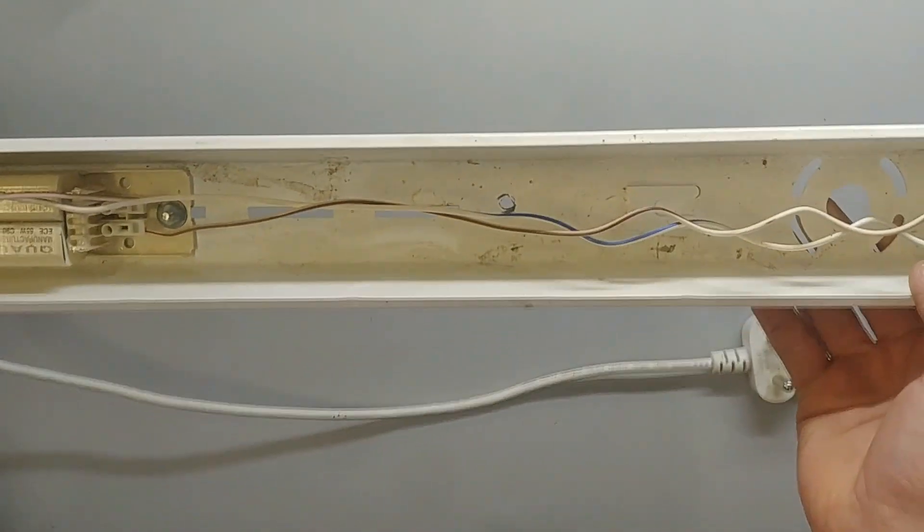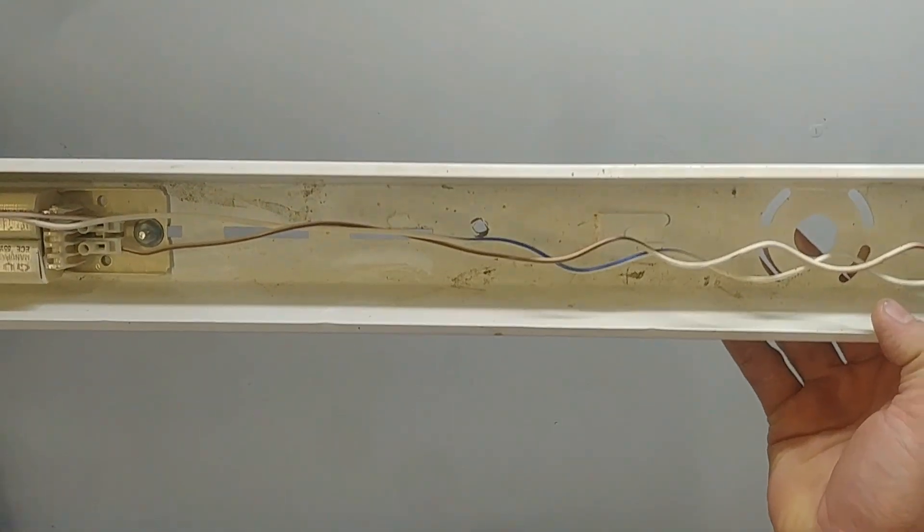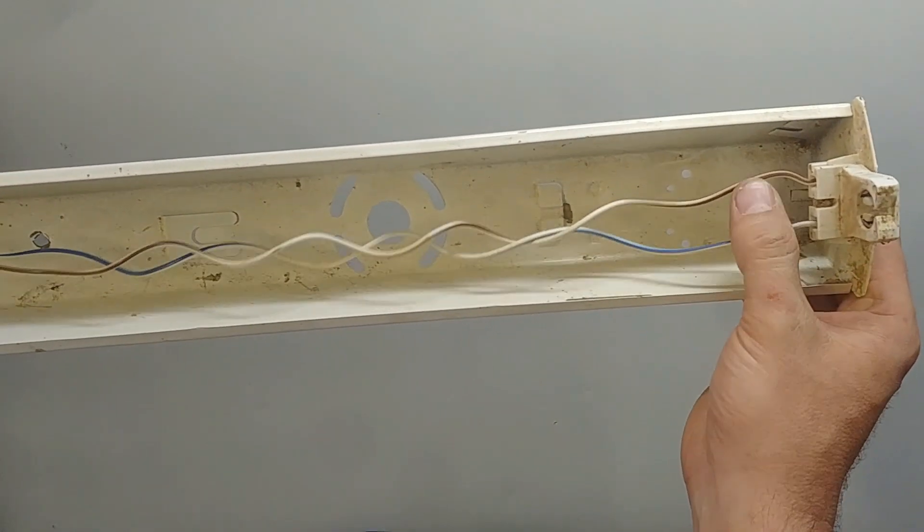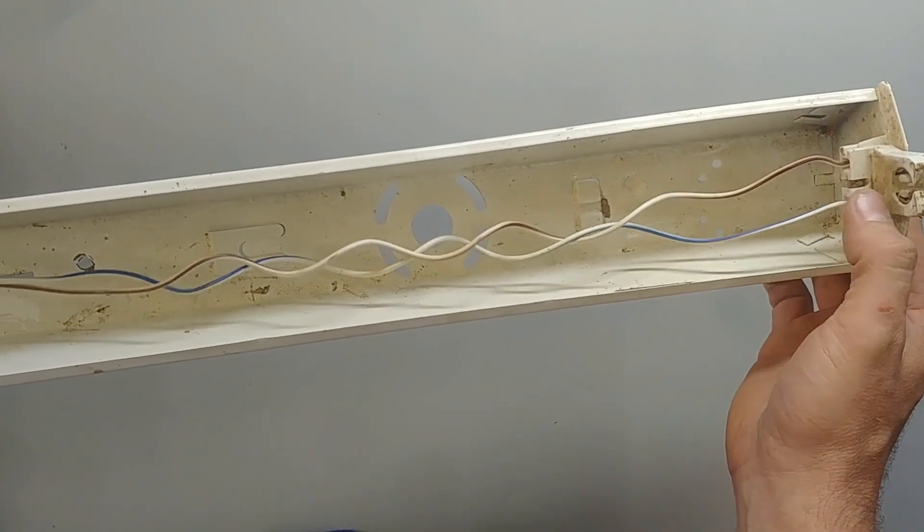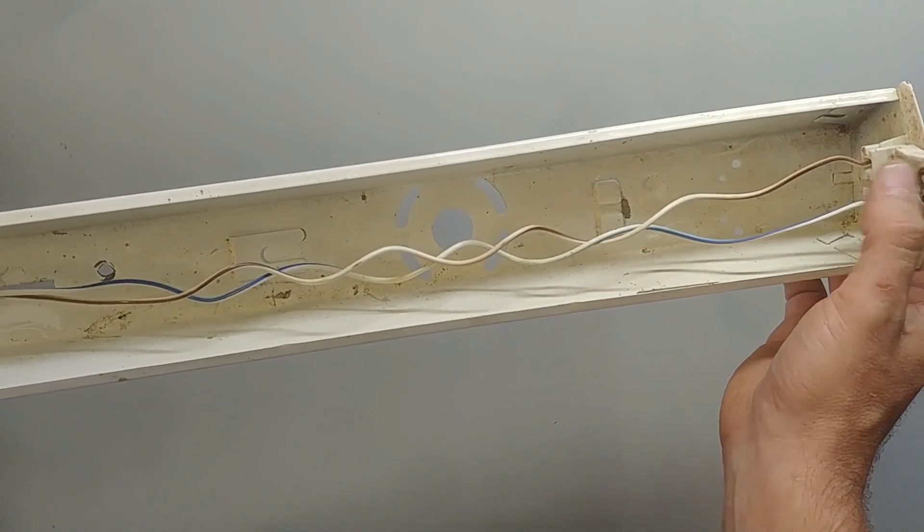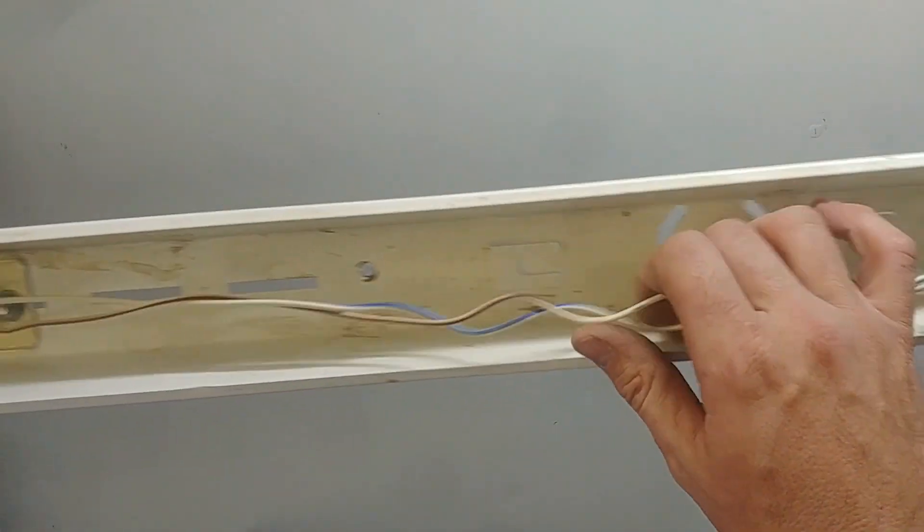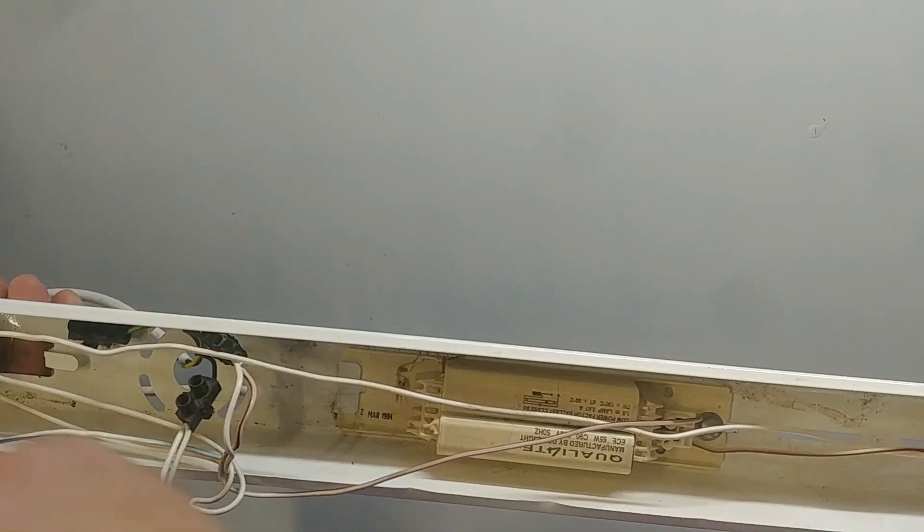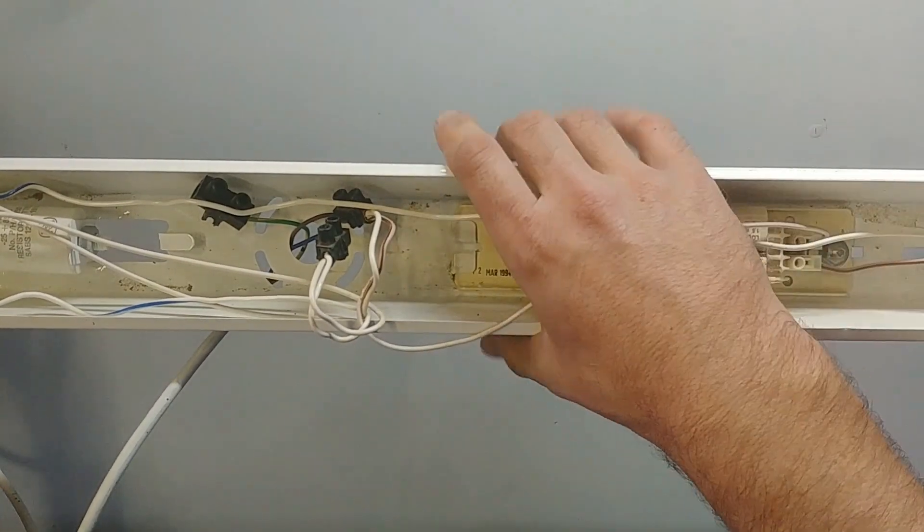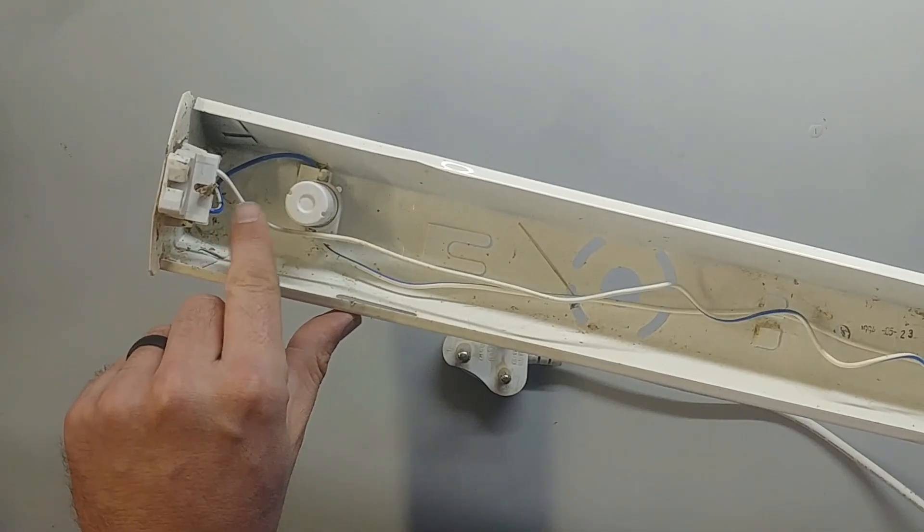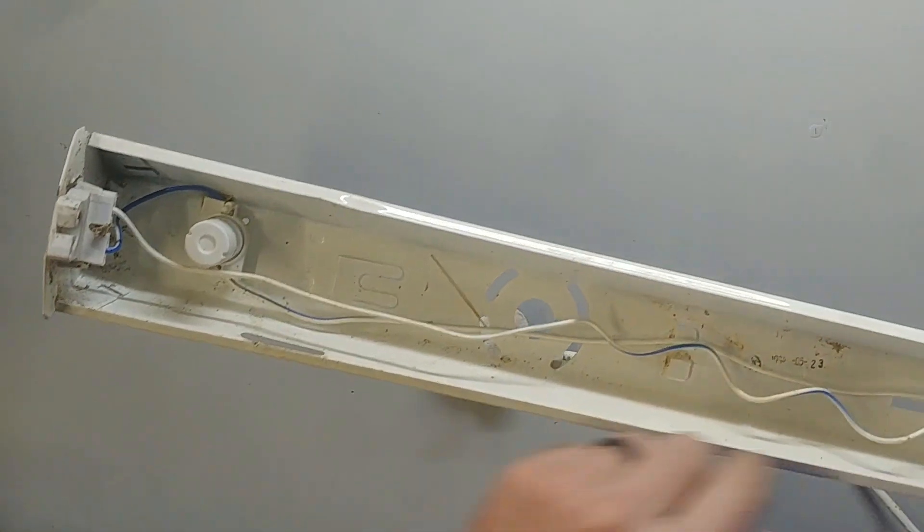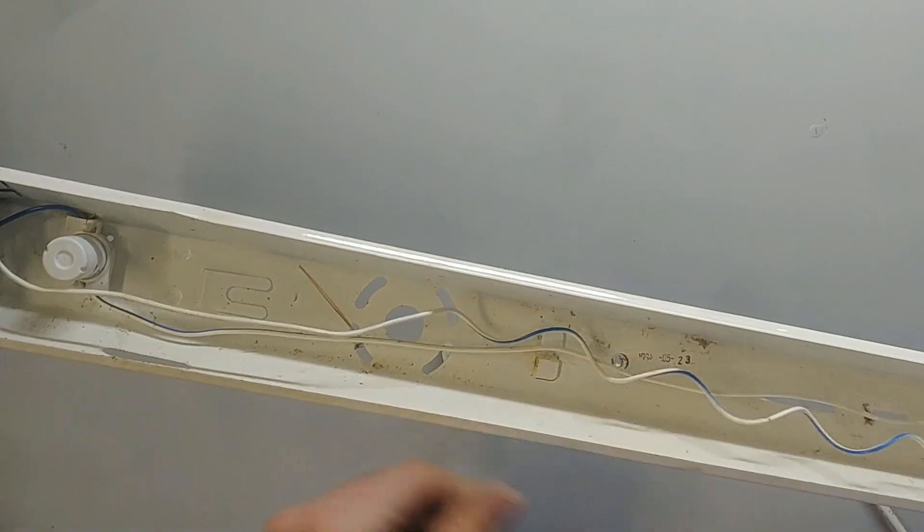So what you need to look for from the start is look at your holder and the wires coming out of there. So this one has one on this side, one on that side, which means one on each of the terminals there. And the wire runs to the ballast, and one goes all the way to the other side holder. And the other end on this side, you've got the holder that goes into the starter, and then out to the terminal. And one wire goes directly to the other side holder.